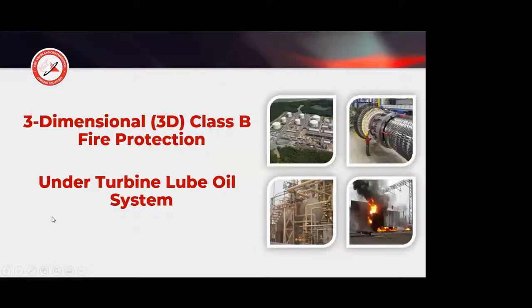Typically you'll have a local design-build fire protection contractor, and we work with them on getting our equipment in. In this case, we had a contractor who installed all the piping and sprinklers. We provided this component, and some connection components between the agent and the water-driven proportioner. We provide the spill containment in most cases, and the agent. Then we come on site as a subcontractor to them to provide commissioning and certification services.